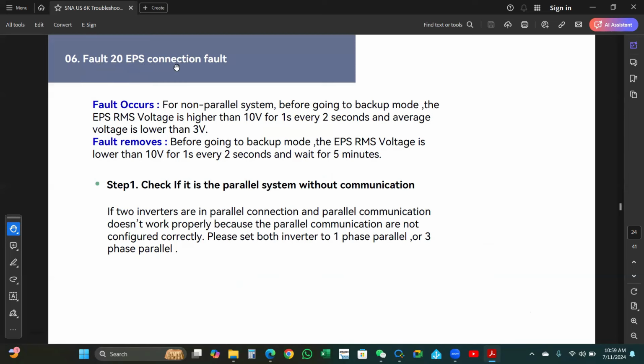Number 6, fault 20, EPS connection fault. The fault occurs for a non-parallel system before going to the backup mode when the EPS RMS voltage is higher than 10 volts for 1 second every 2 seconds and the average voltage is lower than 3 volts. The fault is removed when, before going to backup mode, the EPS RMS voltage is lower than 10 volts for 1 second every 2 seconds and after waiting for 5 minutes. Step 1, check if the parallel system is without communication. If two inverters are in parallel connection and the parallel communication doesn't work properly because it is not configured correctly, please set both inverters to 1-phase parallel or 3-phase parallel.